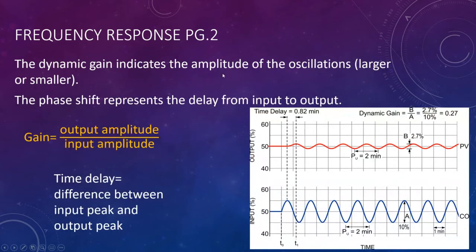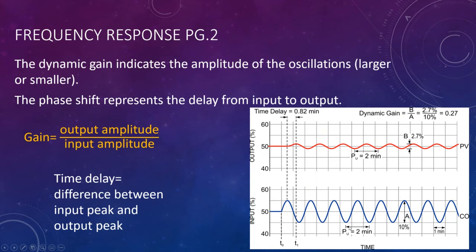Dynamic gain indicates whether output oscillation amplitude is larger or smaller than the input. Phase shift represents the delay from input to output — in this example, 0.82 minutes. These are the two basic formulas we'll use throughout the ILM. As frequency and ultimate period change, this affects phase shift and the process's ability to meet its gain.